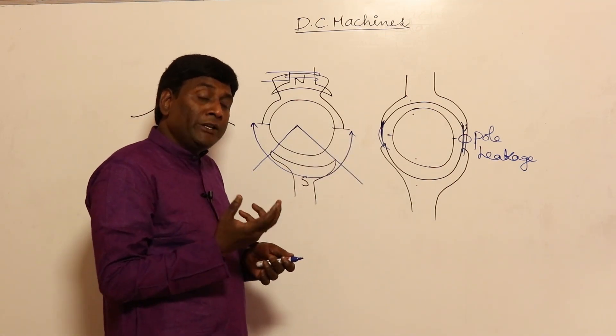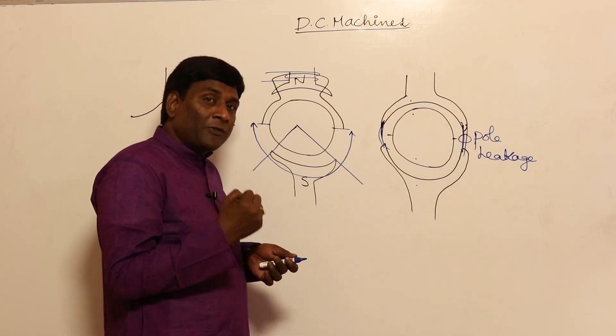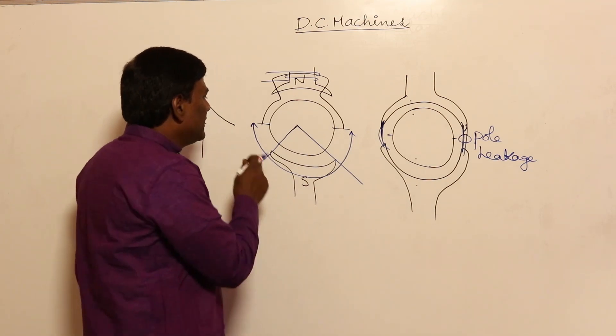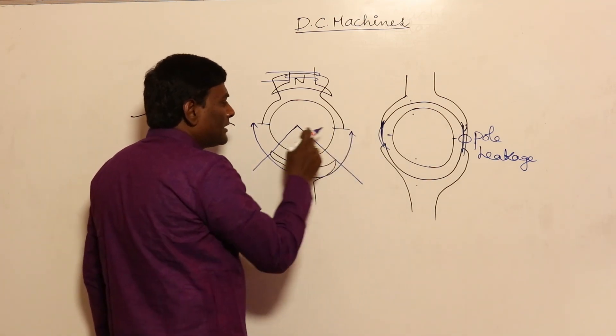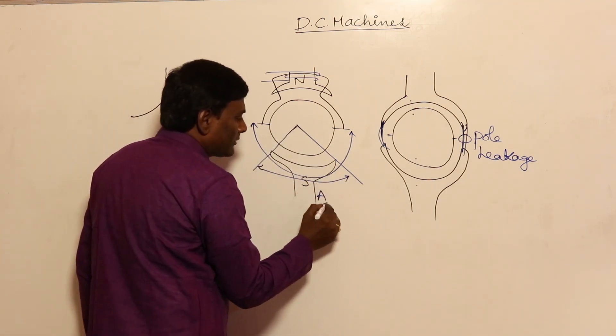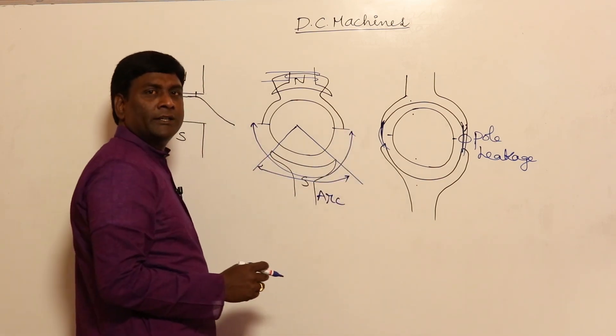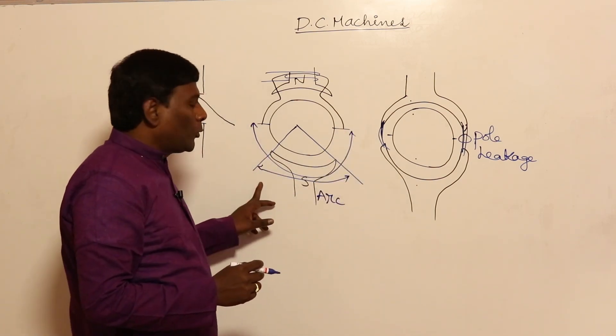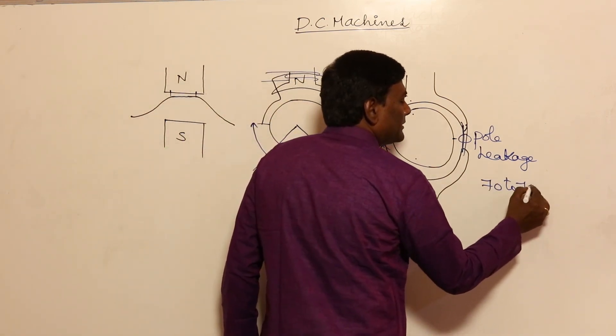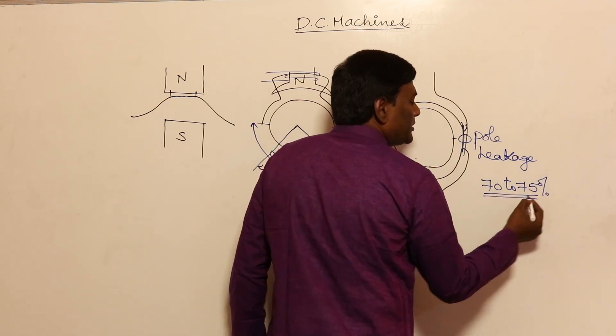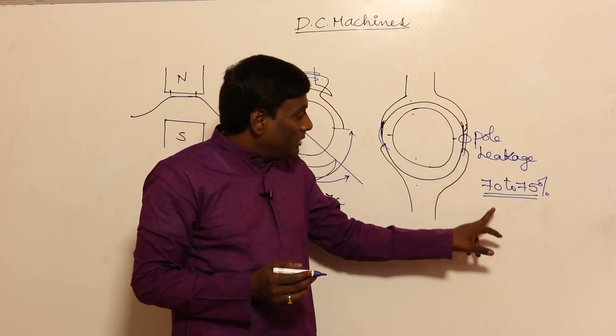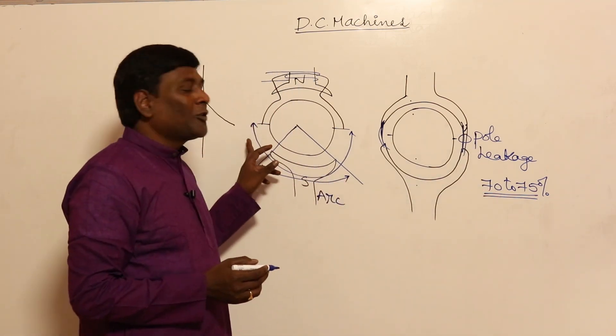So there is a trade-off: in order to increase flat-topness of the pole, the pole arc to pole pitch ratio should be increased; but to reduce pole leakage, it should be less. That is why, if the total pole pitch is 180 degrees electrical, the pole arc to pole pitch ratio should not be more than 70 to 75 percent. Because if you cross this, pole leakage will increase; but if you reduce it too much, flat-topness will be reduced.